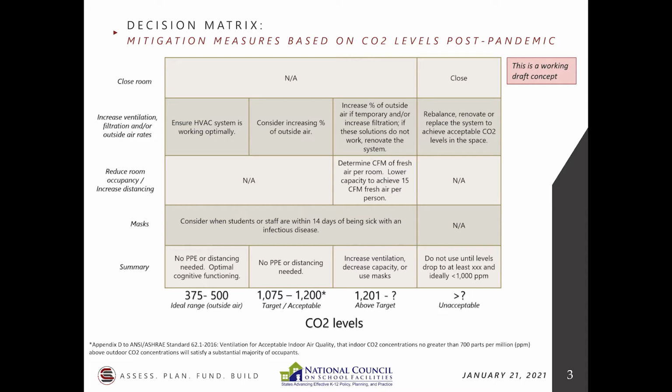Understanding that you don't, you have to take all the other factors into account, and then what are you left with? How do you make your decisions based on that? So the loading, the density or concentration rather of CO2 in adjacent classrooms in these multi-zone systems can influence it. So would it be safe to say that testing at different times of the day in different loading situations would be a best practice in that case, so you're not relying on a single snapshot?